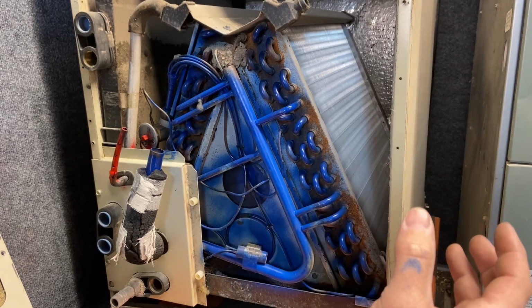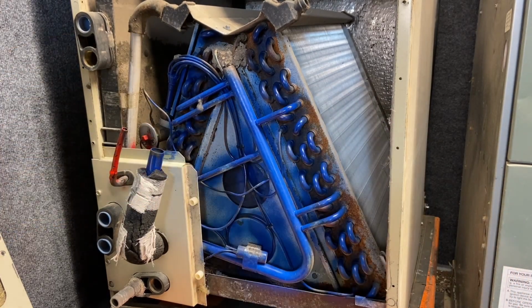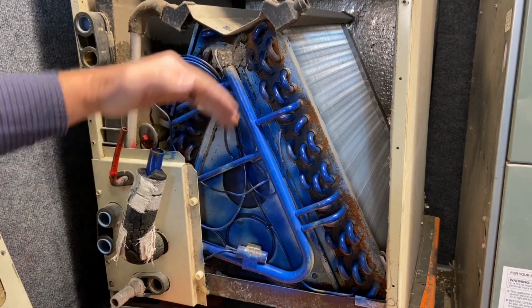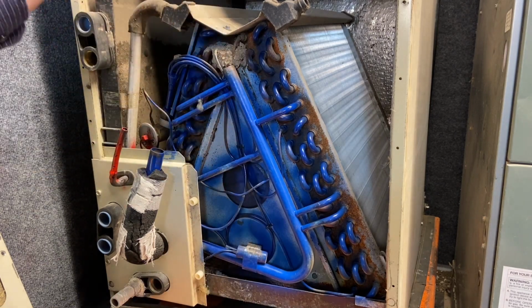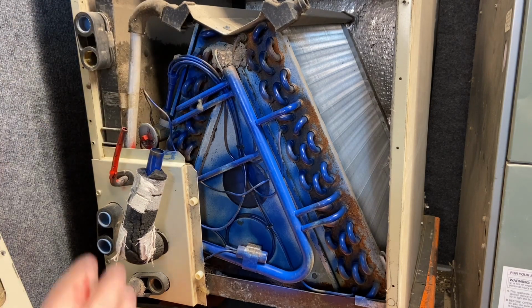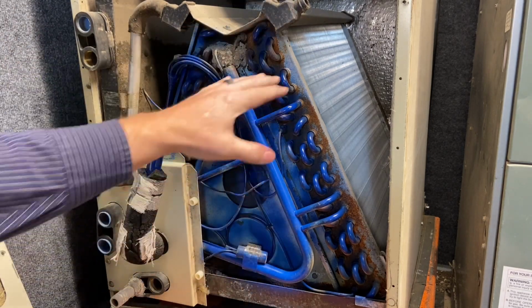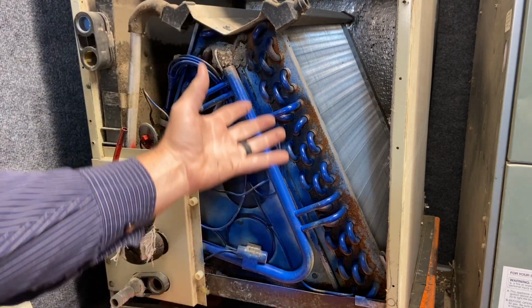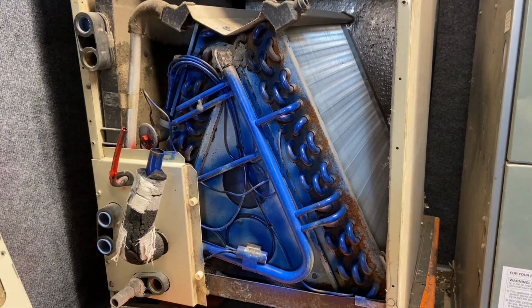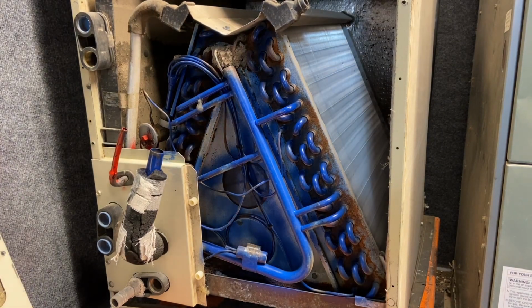Now as we take heat away from the air, the temperature of the air drops. I've taken heat energy out of the air and put it into the refrigerant. So the air comes out cooler. So we're only cooling the air by removing heat from it. That's the first law of thermodynamics. But it's essential that we have airflow across this evaporator coil. In this case, our blower is up here above it, and we're actually pulling air across it. And in other cases, like the gas furnace, the coil is on top, and I'm pushing air across that evaporator coil. It doesn't matter if we pull air or we push air, as long as we get air through the evaporator coil.